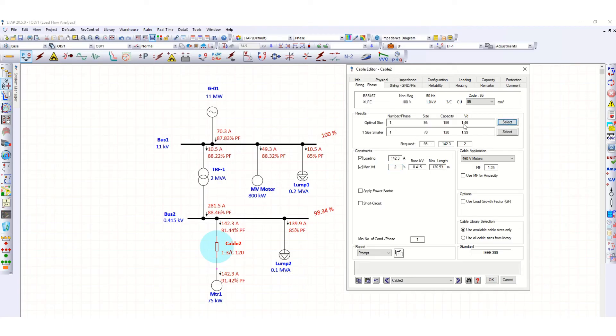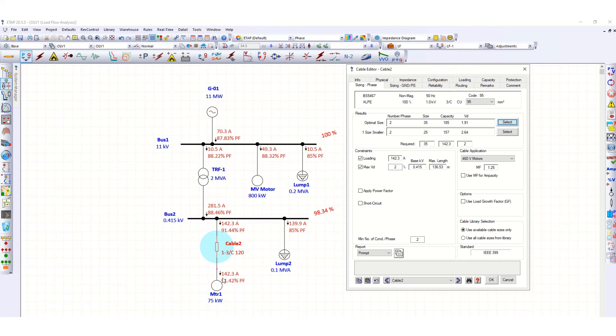Let's experiment a bit. If we change the minimum number of conductors per phase from one to two, the values change. Using two conductors per phase, the size is reduced to 35 square mm with a capacity of 185 ampere — which exceeds our requirement of 142.3 ampere — and the voltage drop is within the 2% maximum limit.